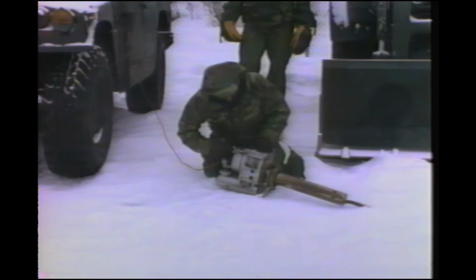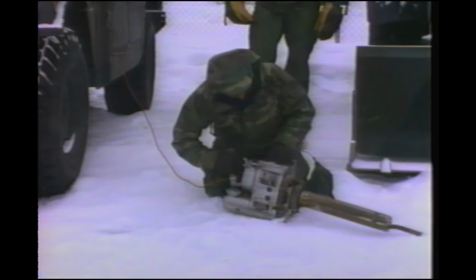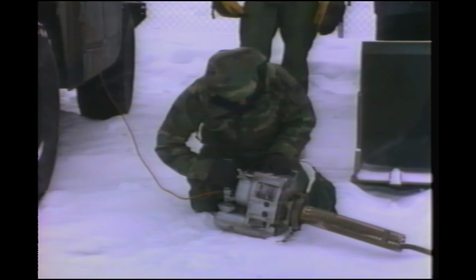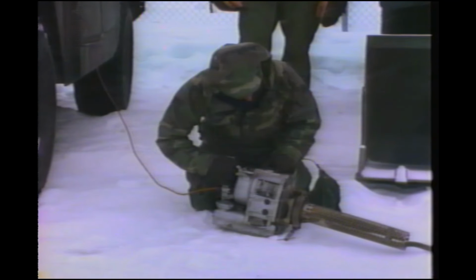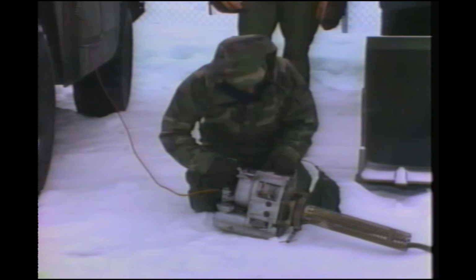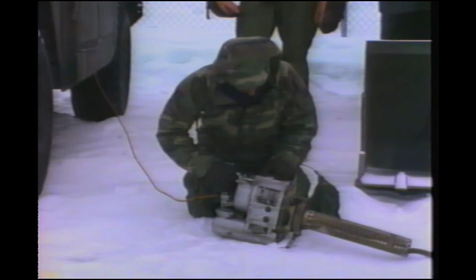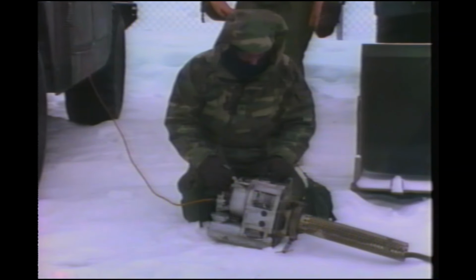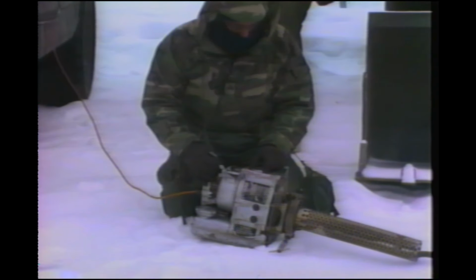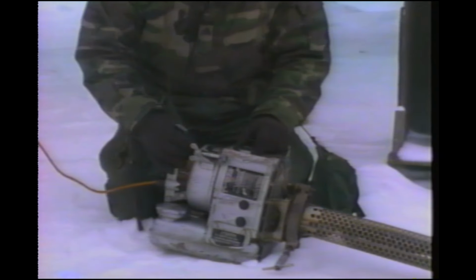While continuing to pump with one hand, open the fuel regulator knob 1/2 to 1 full turn with your other hand. When the first pulsating sounds are heard, continue pumping and adjusting the fuel regulator until sounds come at regular intervals. Then stop pumping. The Swingfire is basically a small jet engine. The fuel regulator knob controls the fuel and air mixture. A warm heater requires less fuel than a cold one, so continue to fine-tune the fuel regulator for 3 to 5 minutes.